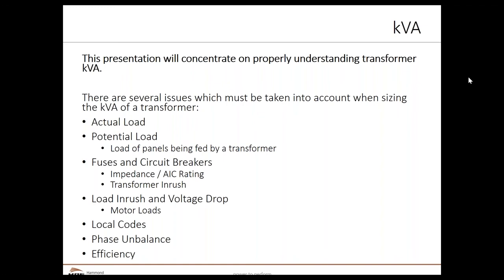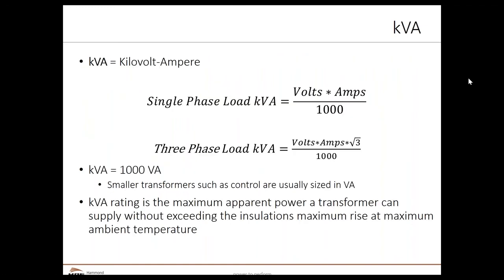I'll start with how we define and mathematically calculate kVA. kVA is the unit of apparent power, which is basically kilovolt-ampere. In a perfect world, apparent power should equal real power, but that's not the case in the real world — we'll discuss that further. You can see on screen the calculation of single-phase and three-phase kVAs. You basically need the voltage and amperes required at the load to do this calculation. You can do this manually using the formula, or use the quick guide on the next slide.